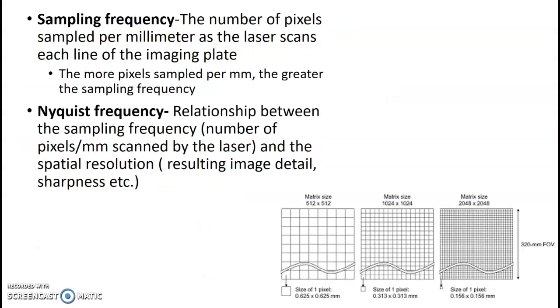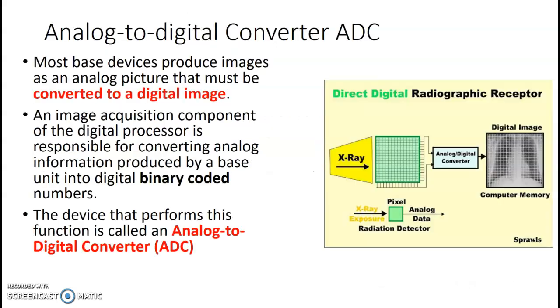Sampling frequency is the number of pixels sampled per millimeter as the laser scans each line of the imaging plate. You might also see the Nyquist frequency — that's the relationship between the sampling frequency and the spatial resolution, which describes how detailed your image is.